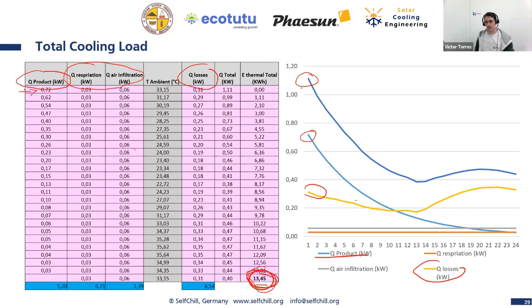Then we have the total cooling load curve, shown here in blue. The total in my Excel calculation came to 13.45, so it's less than what we calculated before. No worries, we will keep using our values. This is just to show you what happens when you calculate it with an Excel file. I can do it hour by hour, and even calculate the whole year, and this is how the curves look in reality.